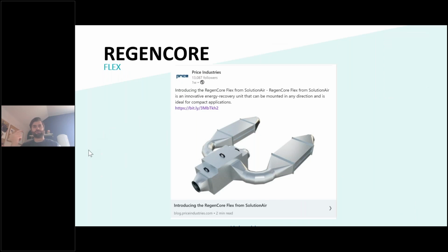This year we launched our Flex unit. It is essentially the same thing as our other units, but it's deconstructed and ducted on site. So within the picture here, you have the 2 core banks on either side of those arms. And then between them, you have your fans and damper section. Those can be placed in any manner, so in any direction or orientation. It can be hung upside down from a ceiling space as well, with access panels beneath it. And then it's ducted however it needs to be as well.